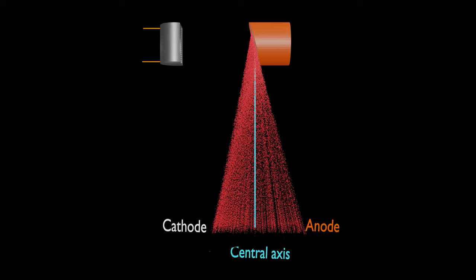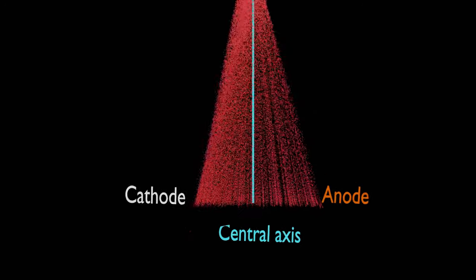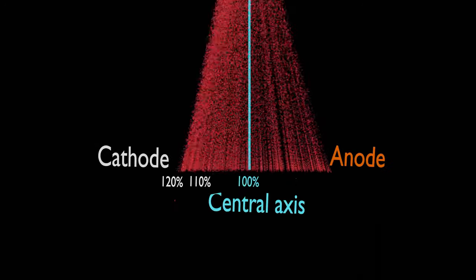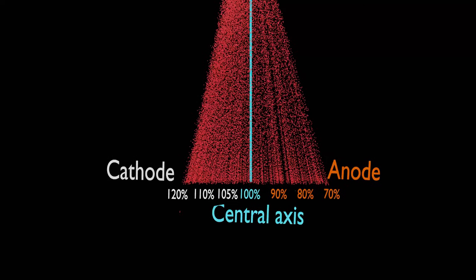The central ray or axis of the useful beam is an imaginary line generated by the centermost x-ray in the beam. If the radiation intensity along the central ray is designated as 100%, then the intensity on the cathode side may be as high as 120%, and that on the anode side may be as low as 70%.